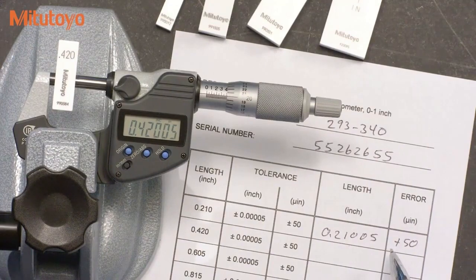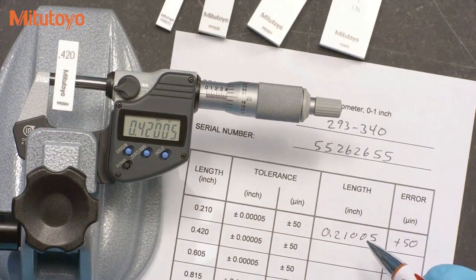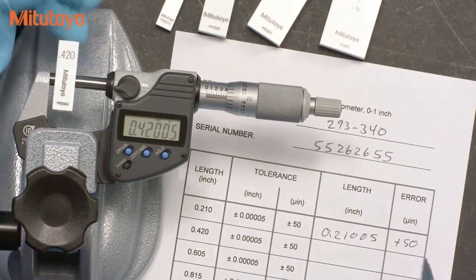Now, if you don't understand millionths or microns, go watch the episode of the Metrology Training Lab that covers units of measure. I'm using this data sheet that we use in some of our calibration classes, and it's just for training purposes. You can use any sort of form that you like. I'll write down the entire value in inches and the error in millionths. For this digital micrometer, the tolerance is plus or minus 50 millionths or plus or minus 1 micron in metric, which is typical for a digital micrometer.